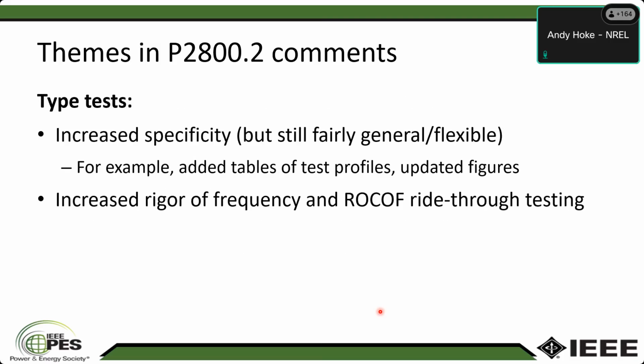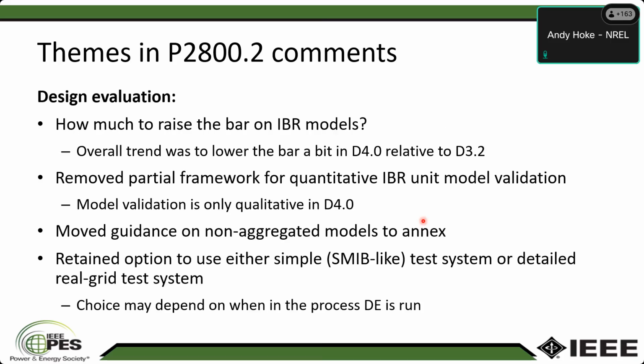You can see that in the type test. There are more details in some of those type tests now. There's more tables and test profiles than there used to be, but not to a huge degree, just slightly more specific, I would say. And there's also a little bit more rigor for frequency and rate of change of frequency ride-through testing. We kind of came to this conclusion that these things are pretty hard to test in a commissioning test. They're pretty hard to test in the field. And so the time to try and make sure that at least the inverter can ride through a frequency or a rate of change of frequency event is in the lab. So there's a little bit more rigorous checking of that now in the type test. There's a whole bunch of other changes, but that's sort of the two that jumped out at me as worth calling out. When we get to the design evaluation, the modeling and simulation, again, we're trying to deal there with this question of how high do we raise the bar?